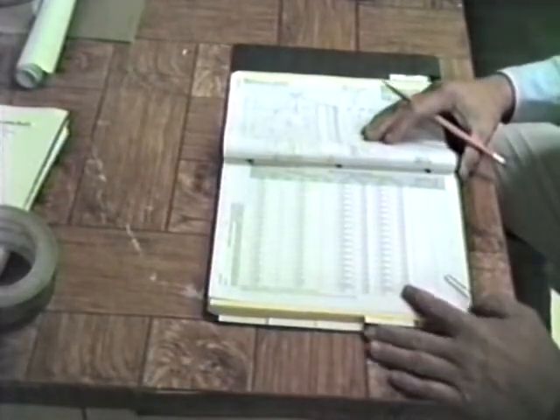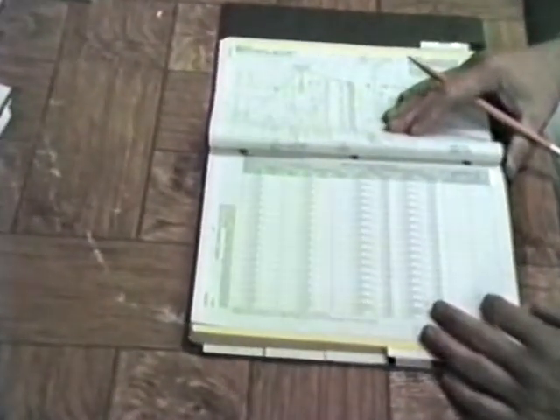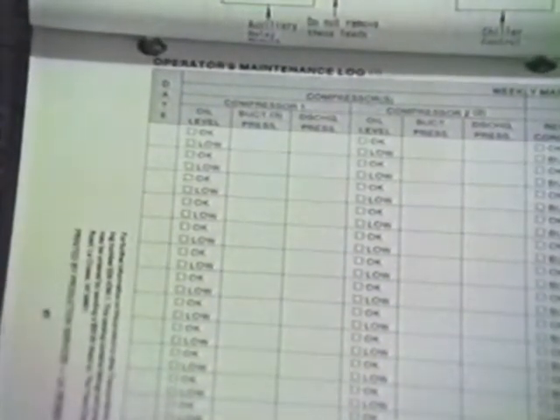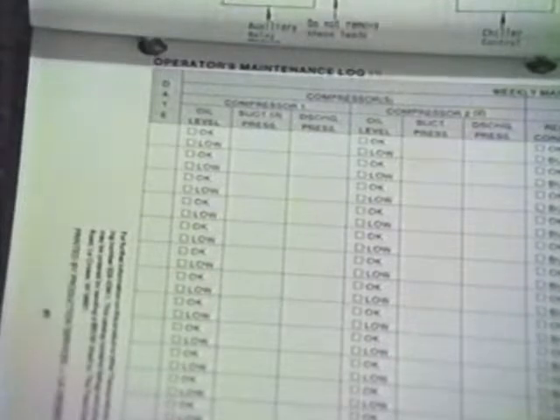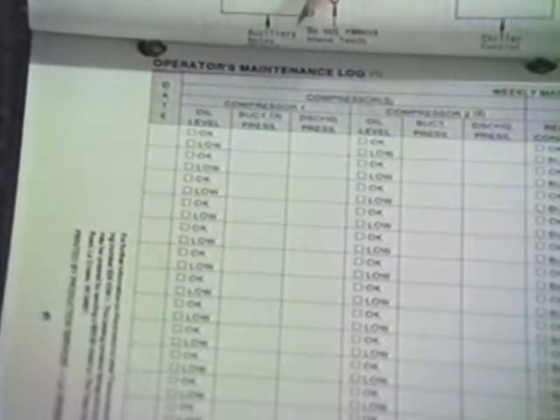Let's look at our operations manual in the chiller section on page 41. They've included an operator's maintenance log. We strongly recommend that whoever attends to the equipment use this as a guideline for their weekly, monthly, whatever routine inspection visits. The chart actually shows a weekly maintenance inspection. It gives a checkpoint block to register the conditions for compressor 1, compressor 2, the refrigerant pressures, suction, discharge, the oil level. There is a place for the condition of the sight glasses on each refrigerant circuit, and also a place on the side over here for the entering and leaving chilled water temperature.